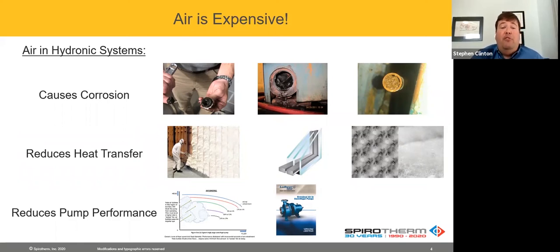The other thing is it reduces heat transfer. That's the most important thing to walk away from today: air is an insulator, and it's been used for a long time for that purpose. When we look at a fluid, we're trying to calculate the heat transfer in that fluid - that's mass flow rate times the specific heat of the fluid times the temperature differential. If I have water or any other fluid, it's continually serving, doing what it's supposed to. But if I have an air-water mixture, it significantly reduces the ability of that fluid to transfer heat. Specific heat of water is 4 times that of air, and the density, which goes into the mass flow rate, is 830-something times more dense than air. So air in a system is causing issues with heat transfer.